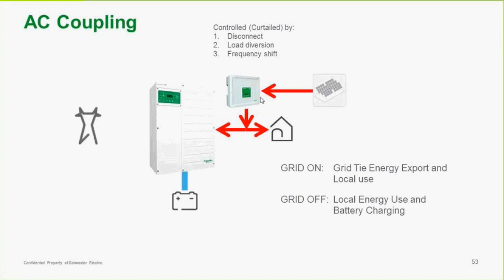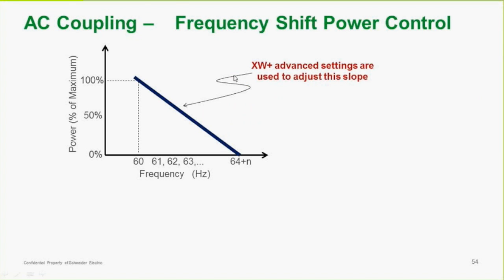And there are a number of schemes to do that. It can be disconnected, or there can be a load diversion where the power is directed to an additional load, perhaps for heating a driveway or using the heat some other way, or just dumping it. And the third way, which is the best way, is frequency shift. The XW Plus does provide frequency shift power control. As you can see, as the power changes, so does the frequency, and as the frequency changes, that controls the grid-tied inverters. Once it goes out of range, the grid-tied inverter will shut down.